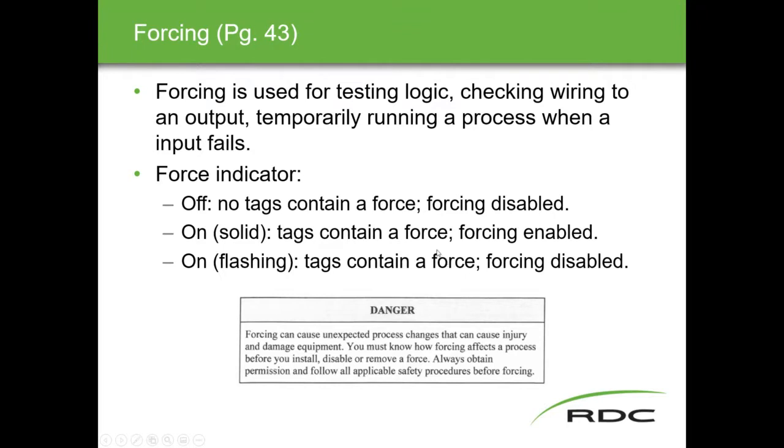Most importantly to remember here, forcing can cause unexpected process changes that can cause injury and damage equipment. You must know how forcing affects a process before you install, disable, or remove a force. Always obtain permission and follow applicable safety procedures before forcing. Generally, if you're a rookie, don't do it.